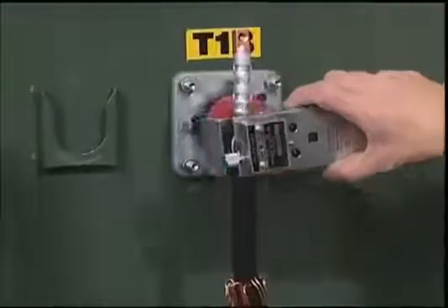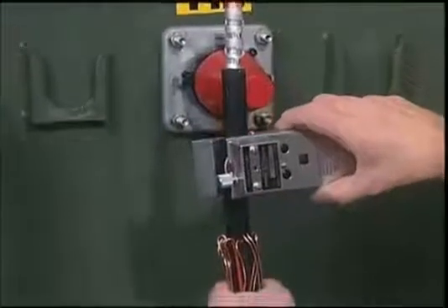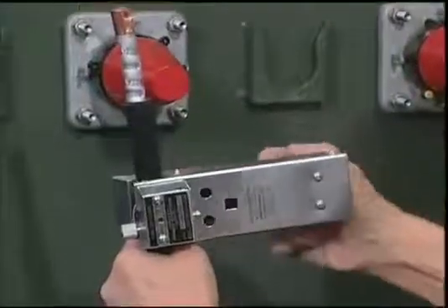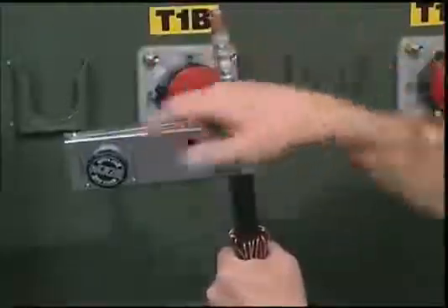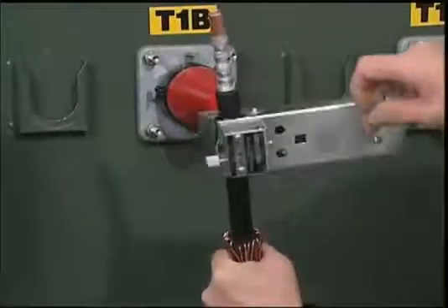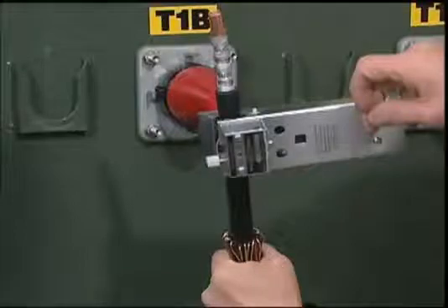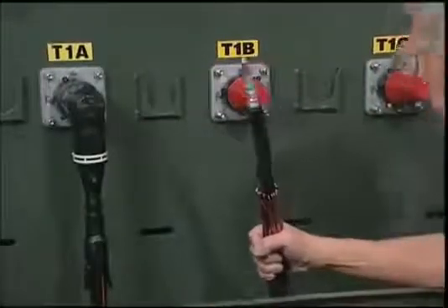Then, back at the actual installation, set the tool to square cut and install on the cable at the 6 7/8 inch mark. Tighten the tool on the cable. Rotate the tool one complete turn to score the cable, and then set the tool to spiral cut and continue turning. Then remove the tool.